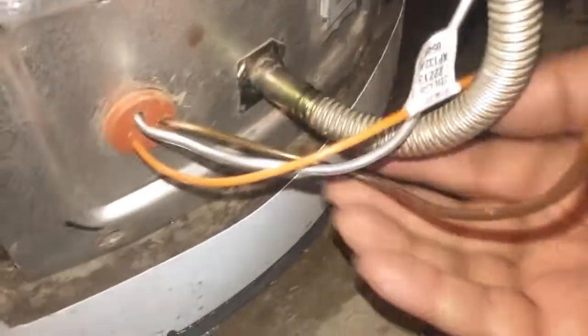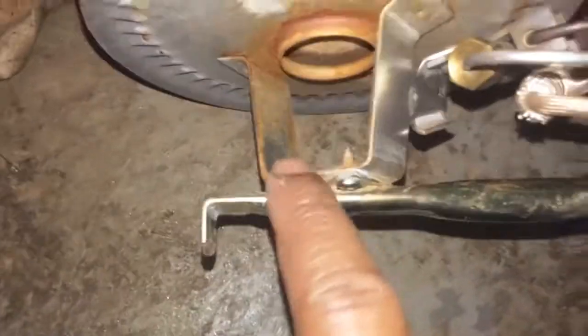Once you have removed the screws, you can pull the burner assembly out, and there is the burner. You can see some stuff falling. So there are the 3 pieces to it. The big burner is right, the opening is right there. You can see if I put it like this, there is where the gas comes out, the main burner gas, and that travels from this line all the way.